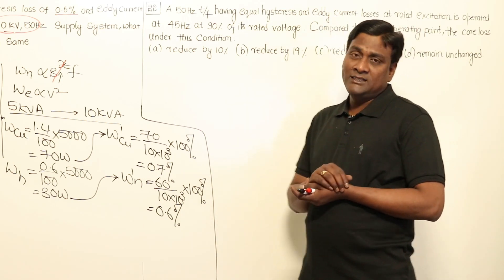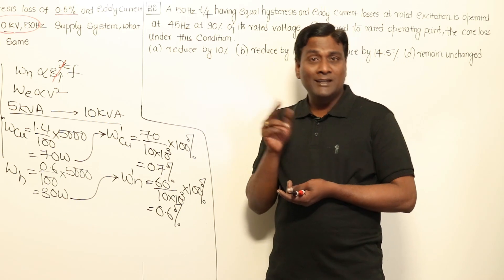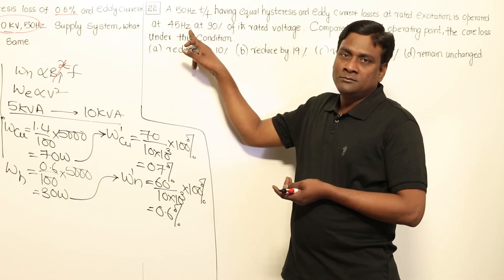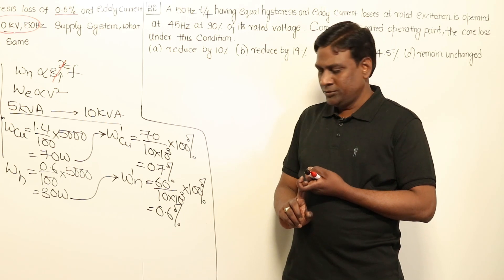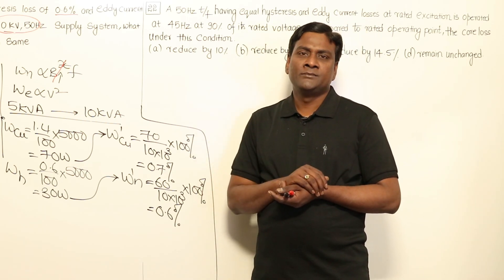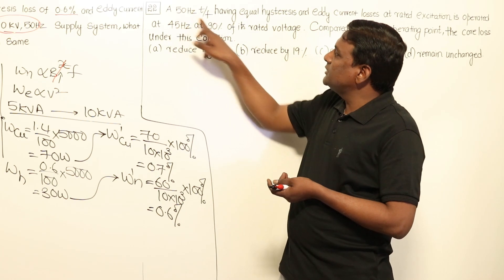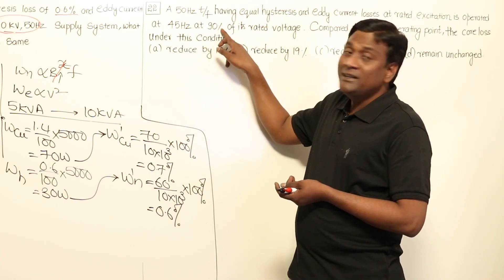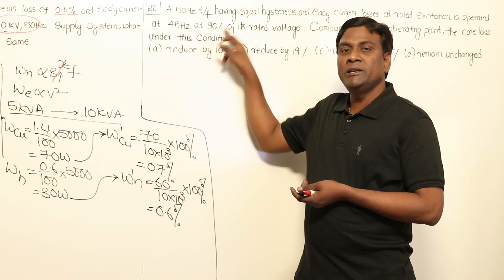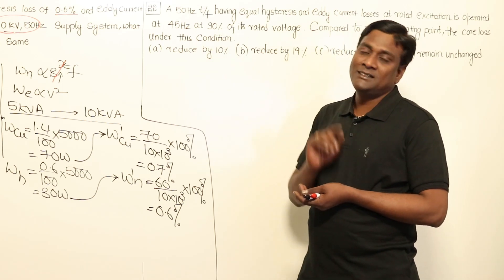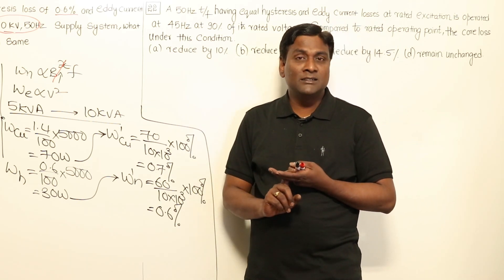So Bmax is constant. Hysteresis loss is directly proportional to Bmax^X × F; since Bmax is constant, it is directly proportional to frequency. Frequency is reduced by 10%, so hysteresis losses reduce by 10%. Eddy current losses are independent of frequency — only dependent on voltage. Voltage is reduced to 90%, so eddy current loss is proportional to 0.9² = 0.81, meaning a 19% reduction in eddy current loss.